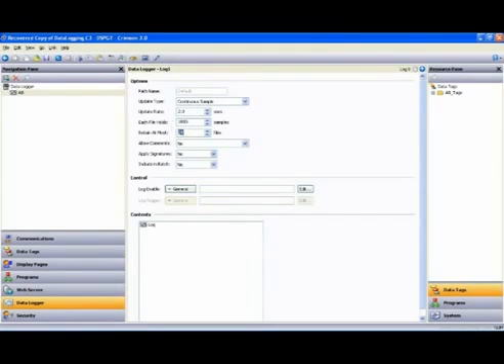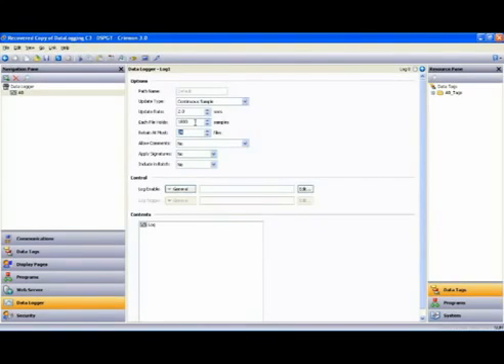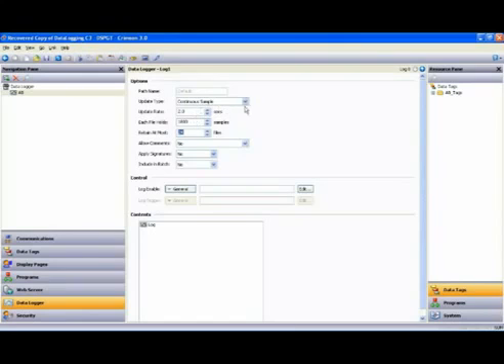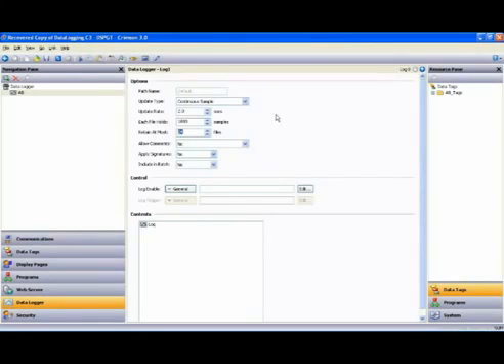So, what we just did in this example is set the Data Logger up to log 24 hours of data with each file representing one hour of samples. Now, since the Data Logger operates on a first-in, first-out basis, when the Data Logger puts the specified number of samples in the last file, it automatically starts overwriting the samples in the first file, so this example always shows the last 24 hours' worth of data.